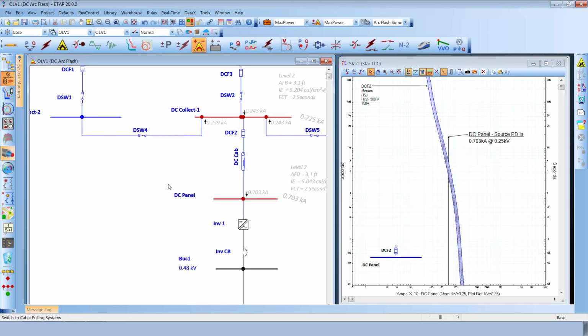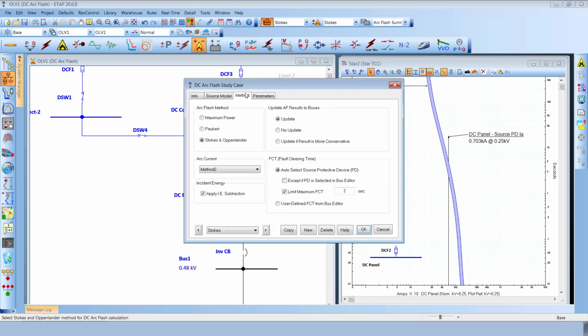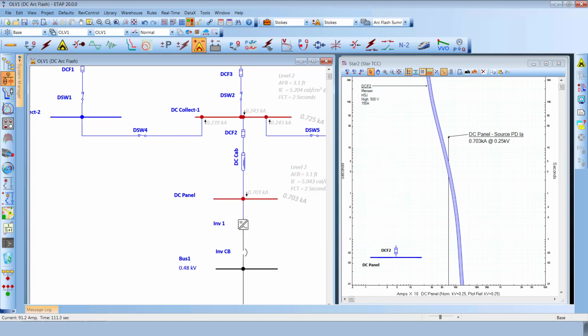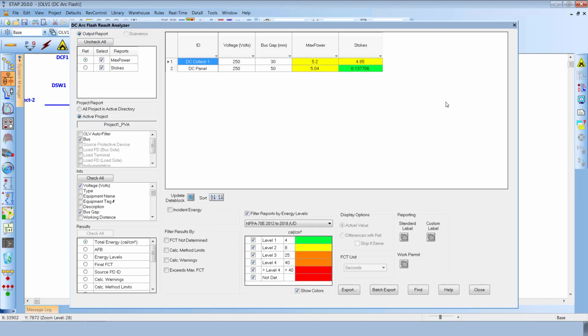Now that we understood the current and the operating time based on the maximum power method for these faulted locations, let us move on to the next method listed in this project, which is nothing but the Stokes and Oppenlander method along with a double iterative technique that Albert has mentioned in the previous slides. Let us run the Stokes method and use the arc flash analyzer to compare the differences between the results for the same locations and analyze the reason behind the reduction in the incident energy and how it is justified based on the short circuit characteristics of the sources in this project.